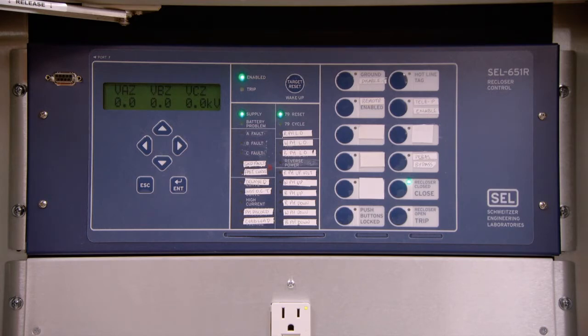Voltage displays. There are 2 voltage displays. The secondary voltage display is supplied from the actual recloser itself from a built-in capacitive voltage supply on the load side of the recloser. The other voltage display is for outside or external potential transformers if used. They would be applied to the source side of the recloser. If you were getting into advanced programming, such as generation connections, you would have both voltage supplies and you would be able to recognize which were there.